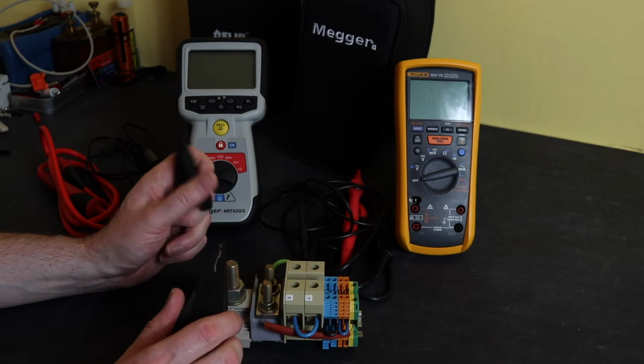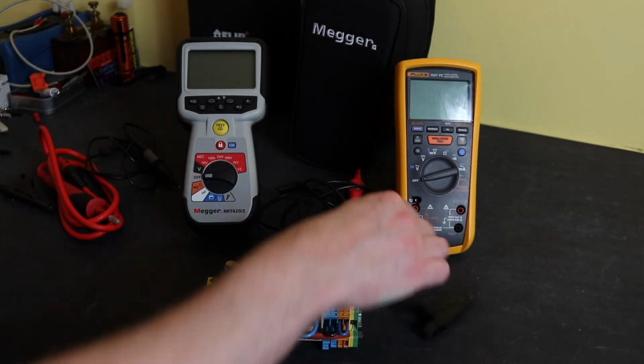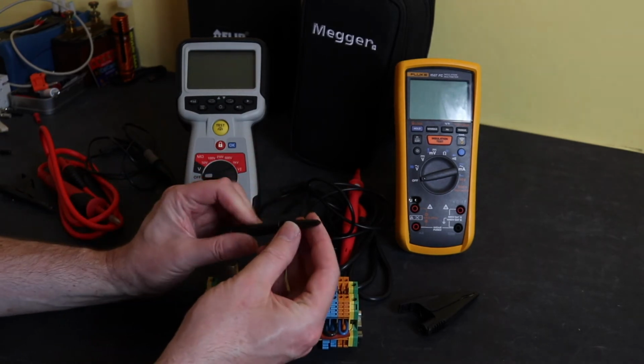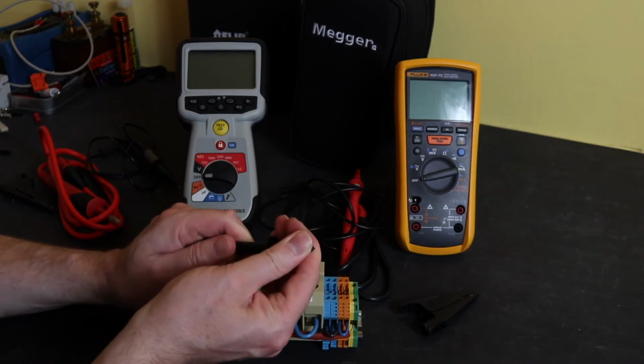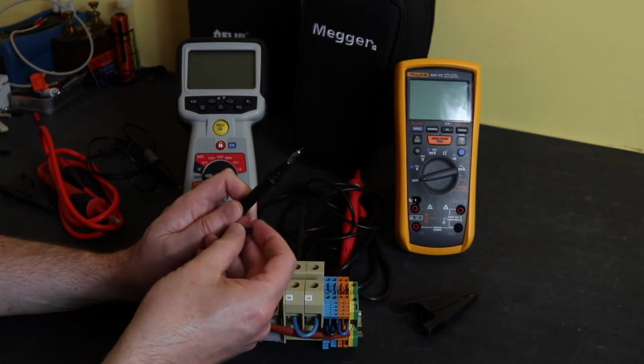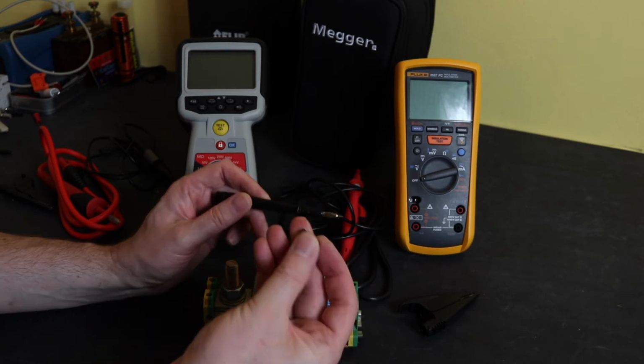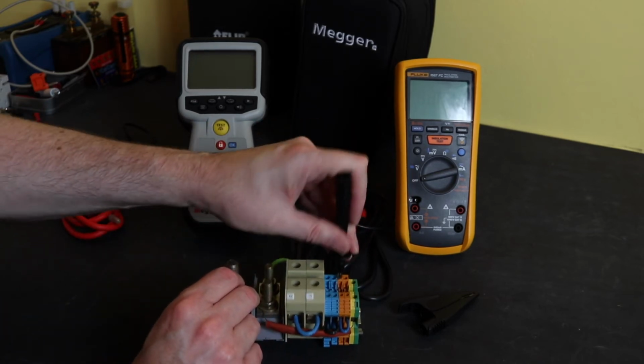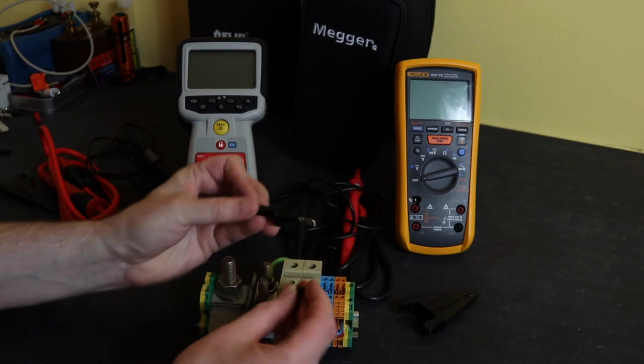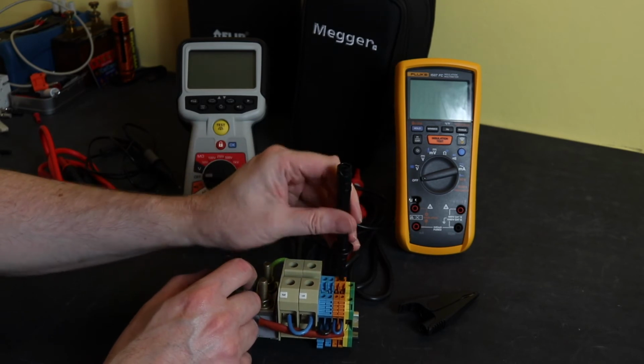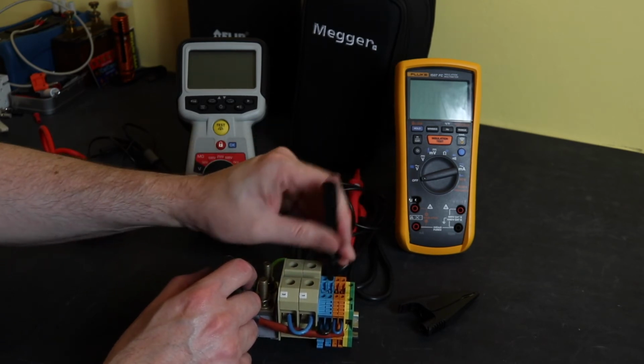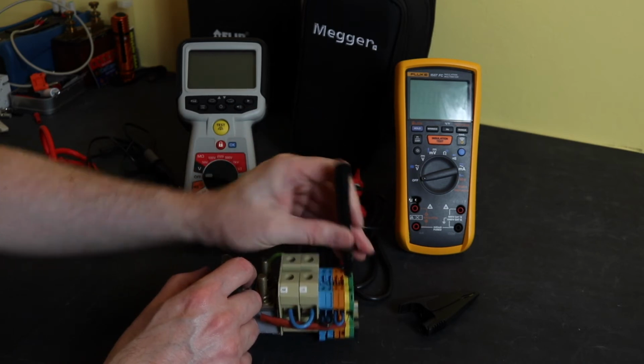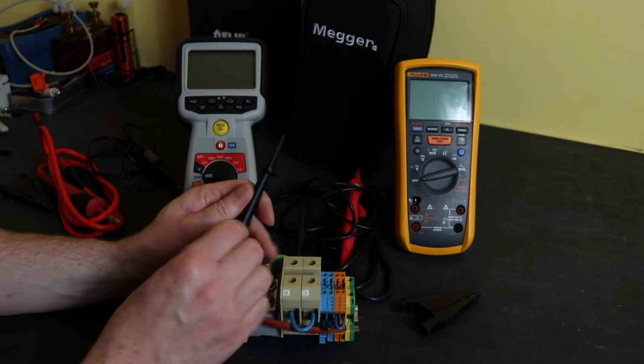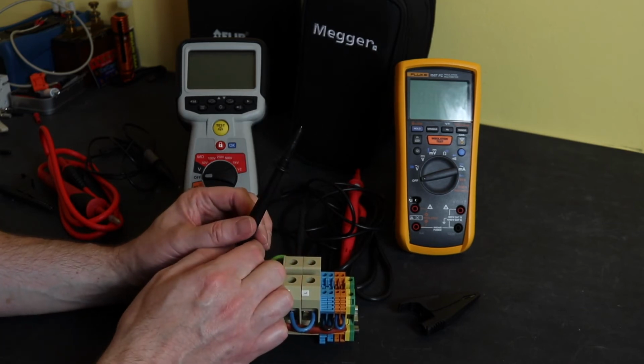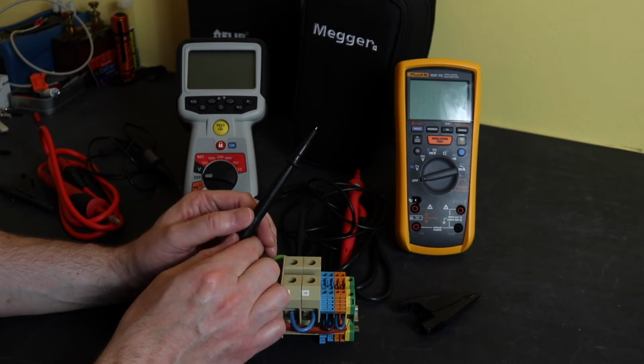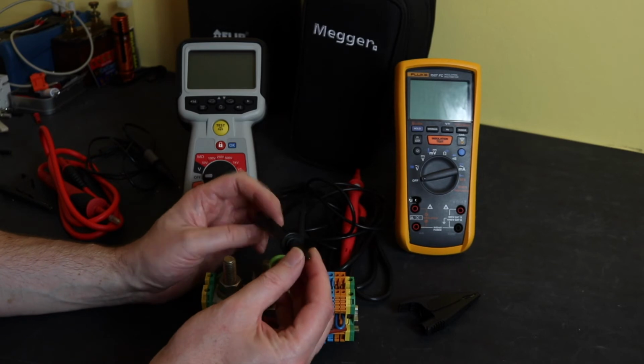But other than that, they're both usable really for the job. The actual probe, this is the one from Fluke, and you can see it's got a removable GS38 cap on here that reveals a 4mm adapter there. So when you take the cap off, you can get into the terminals, no problems. With a cap on, I cannot get into 2.5 there. I can't get into the 4mm. I can get in and make contact with the 6mm, and obviously the 35mm. There is no problem. So yeah, I much prefer the probe tips from Megger, even though they are bespoke to that company.